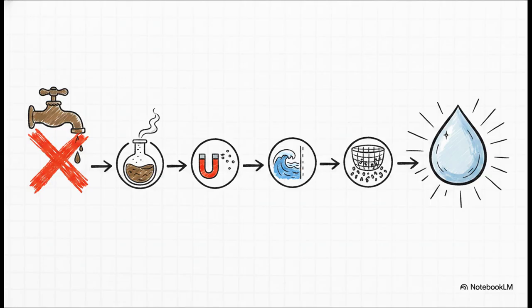Tap water is absolutely useless here. I mean, it's packed full of minerals and organics. Just as an example, the trace calcium found in everyday tap water could falsely trigger a critical hypercalcemia result on a patient's blood test. That could lead to disastrous medical interventions. So we absolutely must use heavily purified water, specifically designated as clinical laboratory reagent water.